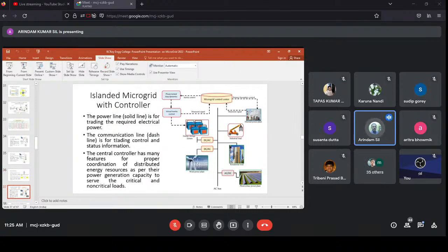Having said that, there is also an operational mode: islanded mode and grid connected mode with controller. In islanded mode microgrid with controller, the power line, shown as a solid line, is for trading the required electrical power. The communication line, shown as a dashed line, is for trading control and status information, that is data assimilation. The central controller has many features for proper coordination of distributed energy resources as per their power generation capacity, to serve the critical and non-critical loads.